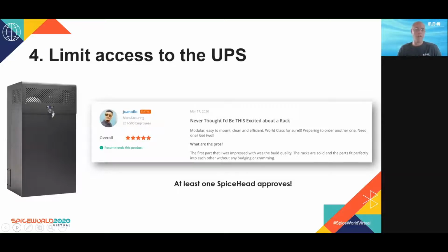So 4, we see limiting access to the UPS. So as Mike mentioned with Linus, a photographer plugged in a 1,000 watt bulb and that triggered the event. Of course, it was more than that. So even so, limiting access is a good idea. We see another example where we had a situation of a cleaning staff plugging in a vacuum cleaner into the UPS. So for smaller UPSs, one possible option is a wall mount enclosure for secure installation.